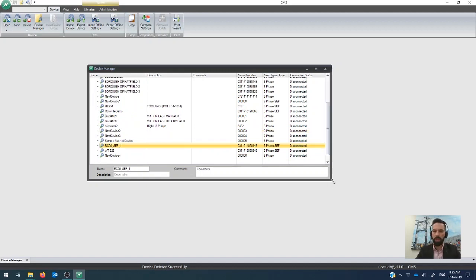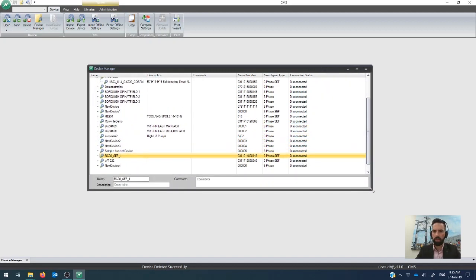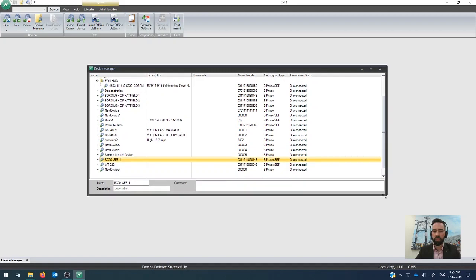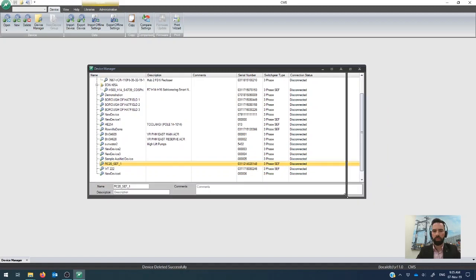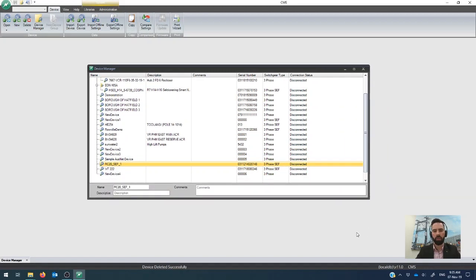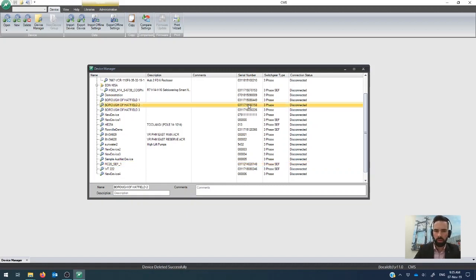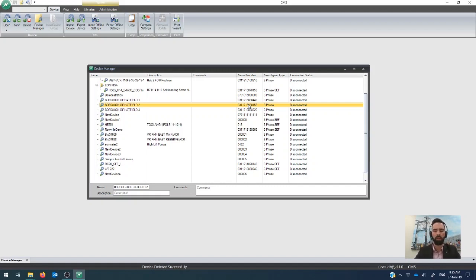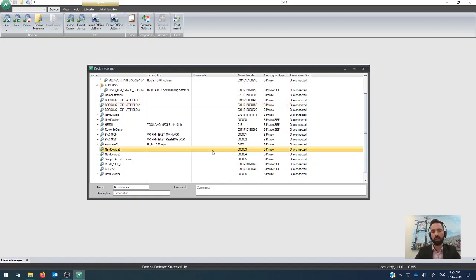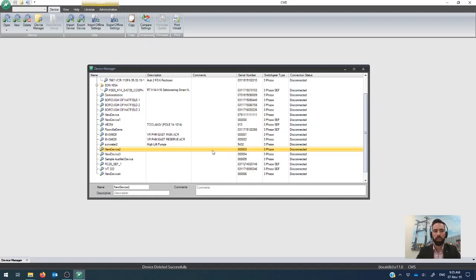A template file is something that you typically use when you're working to create a bunch of settings that you're going to distribute to somebody else. The important thing with the device file is that if you actually want to connect to a field device, the serial number of the device file has to match the serial number of the relay in the field to make sure that the settings go into the right place. So if you're making a template, then it's basically just a blank device file except for the offline settings that you can use to copy across to live devices. So let's start with that on how to create the template file.